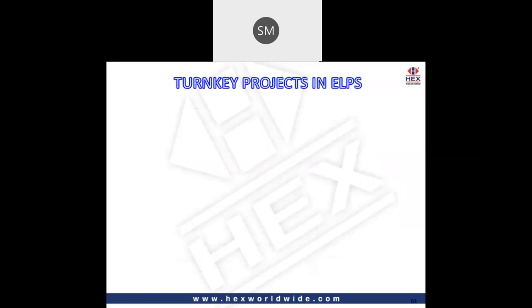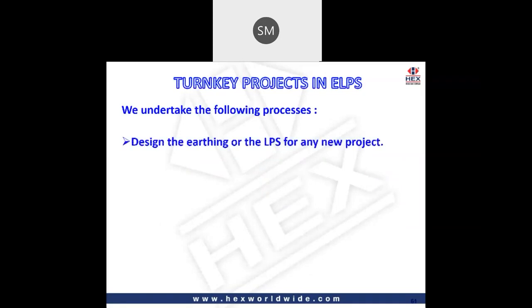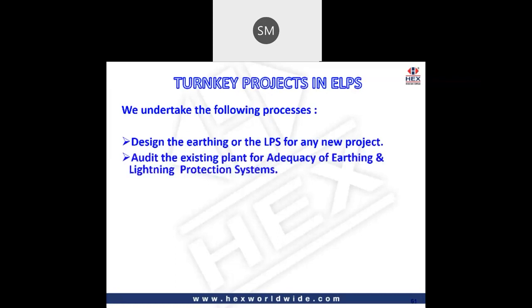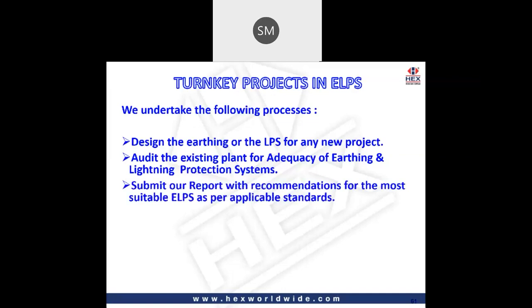Well, moving on, what can HEX do? HEX has the capability to undertake the following activities. We design the earthing for all the lightning protection systems for any new project, or we can audit the existing plant or facility for the adequacy of earthing and lightning protection systems according to the relevant standards. Then we submit our report with recommendations for how to improve it or get it as per the applicable standards.